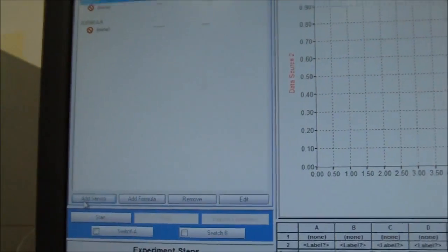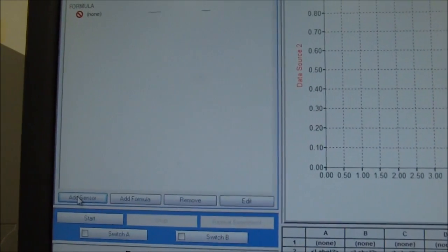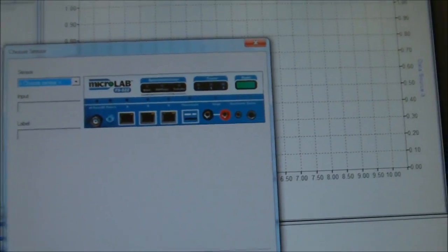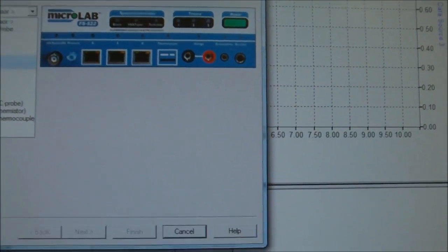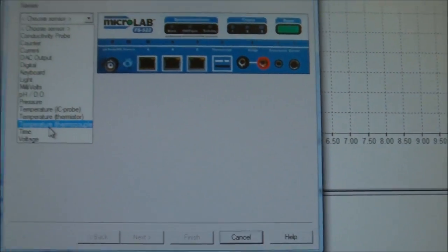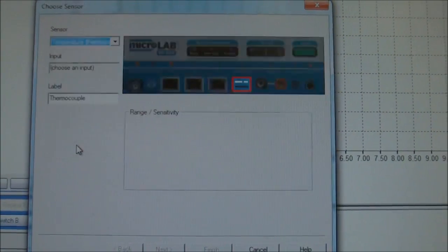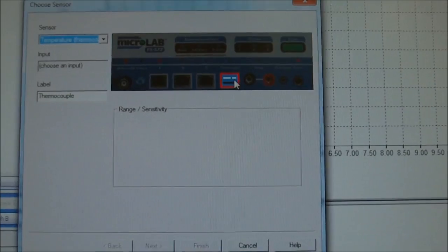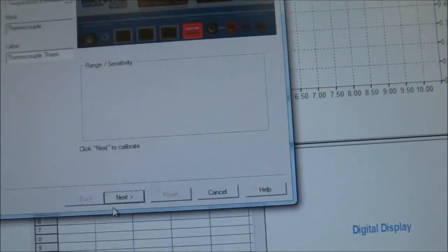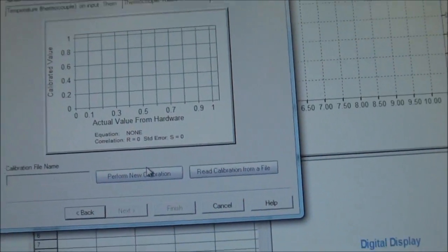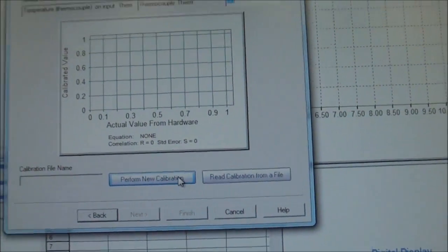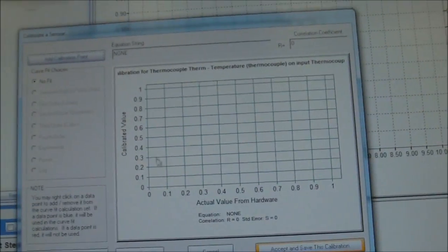So we go to this part of the screen here and we click Add Sensor, and then it brings up this window, and here we choose the sensor, which is the temperature thermocouple. All right, and then this part right here lights up. Click that because that's where we have it plugged into, right? Click there. We go next to calibrate this. We're going to perform a new calibration. So we perform a new calibration.